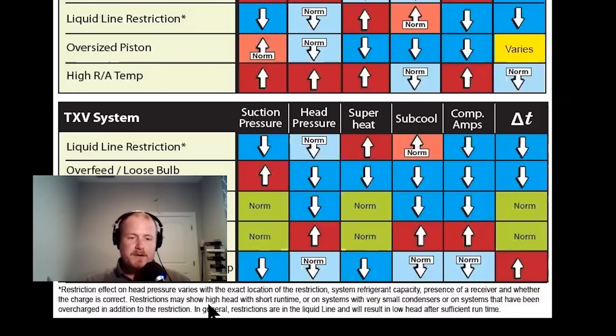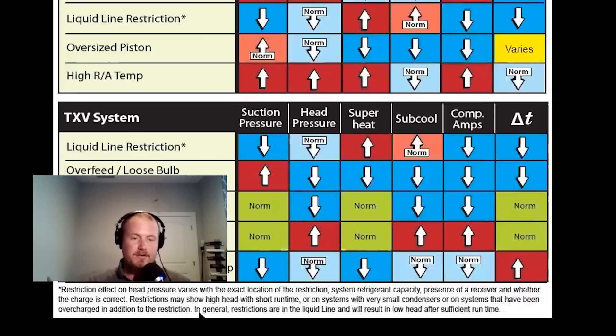So restrictions may show high head pressure with short runtime, or on systems with very small condensers, or on systems that have been overcharged in addition to the restriction. In general, restrictions in the liquid line will result in low head pressure after sufficient runtime.